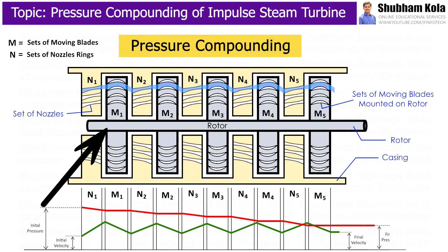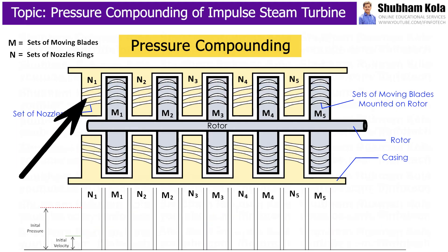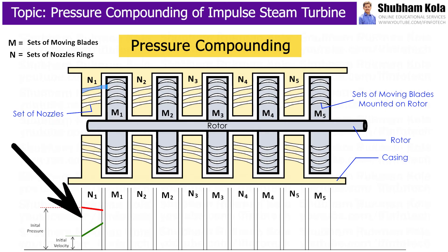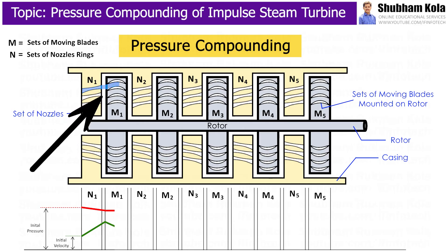During working of the pressure compounded steam turbine, high-pressure steam enters into the turbine. Here, steam gets partly expanded in the first set of nozzles, thus the pressure of steam decreases and velocity of steam increases. This high-velocity steam is then passed over the first set of moving blades M1, where the kinetic energy of steam is utilized to rotate the moving blades.